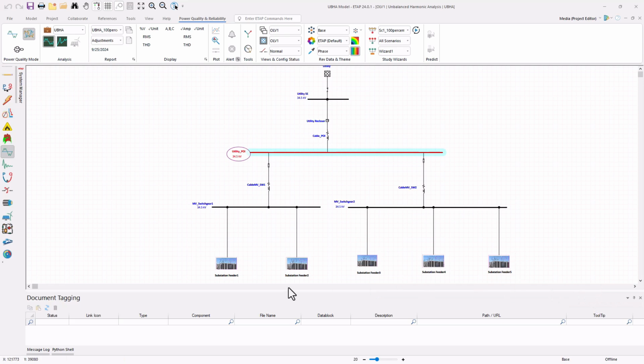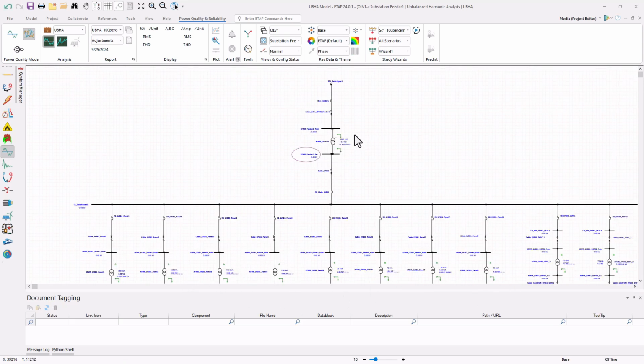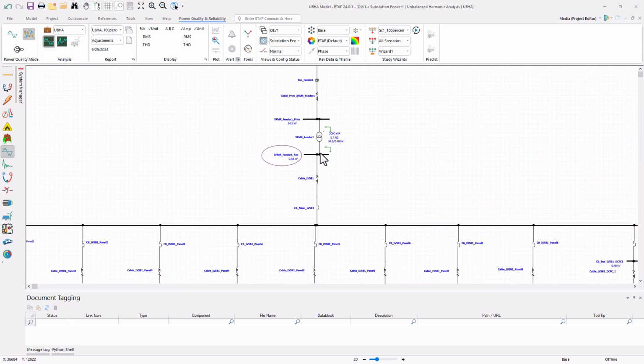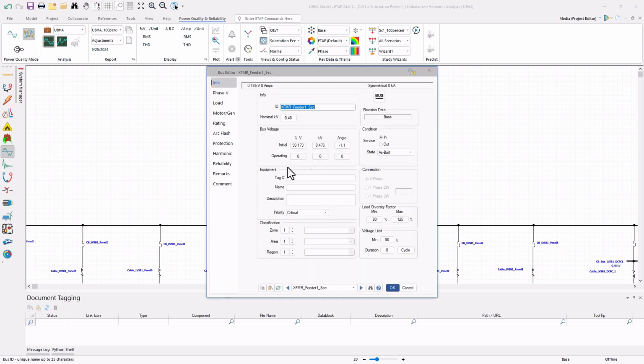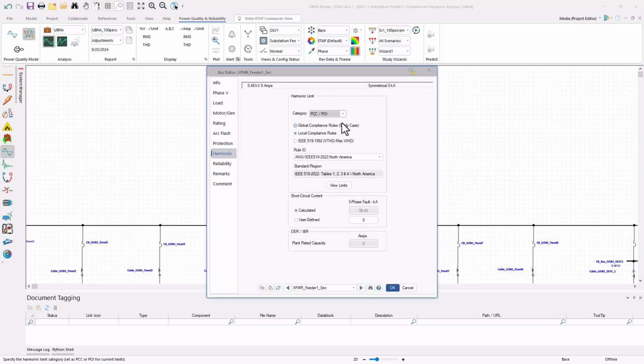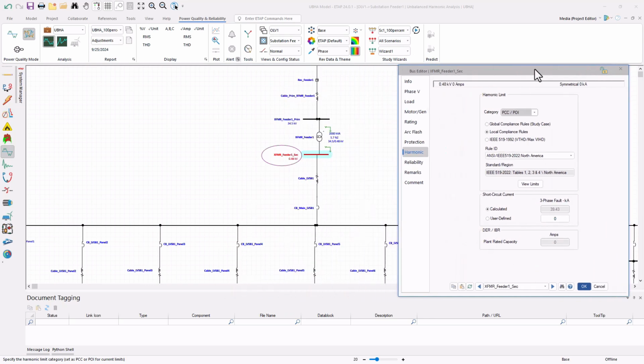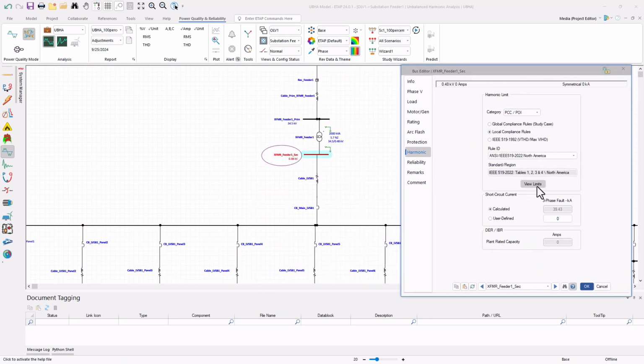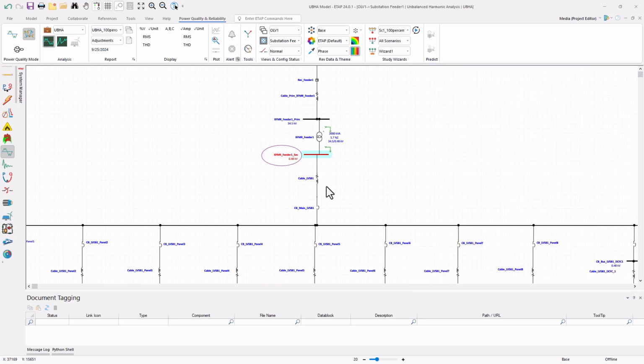We have 5 substation composites here. Going into each one of them, we'll have the service entrance transformer. Secondary of each of those transformers are the locations where the results were analyzed. Let's take a quick look at the harmonics page of one of these buses, set up to PCC/POI with the rulebook set up to compare the distortion results of bus voltage distortion results against the voltage limits from this rulebook and the current distortion limits at the connected branch to the current distortion limit set up in that rulebook.